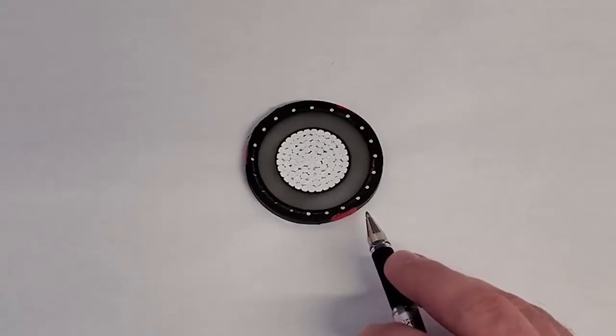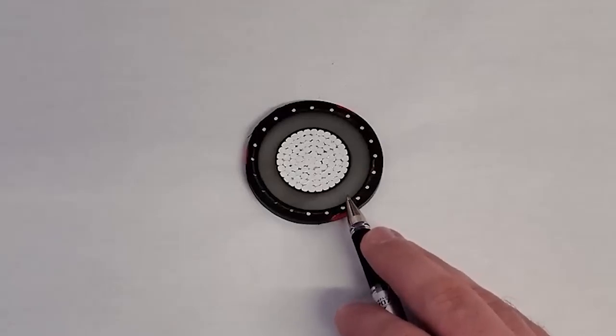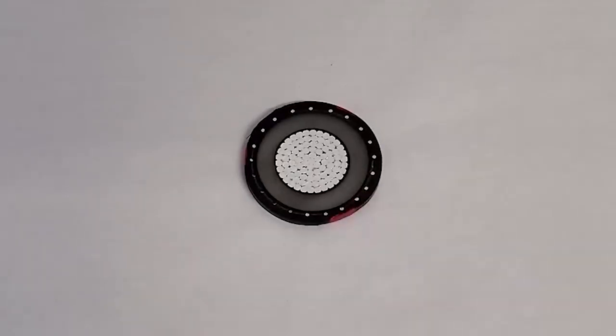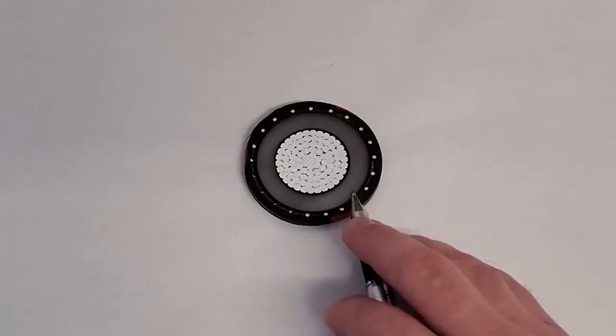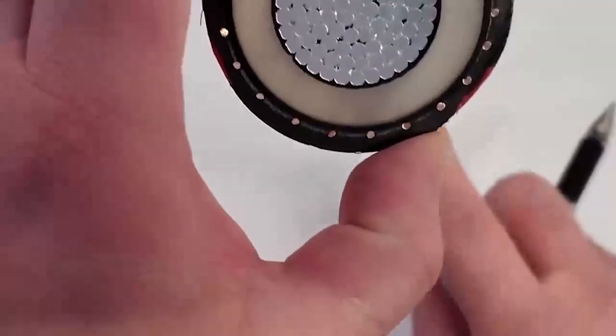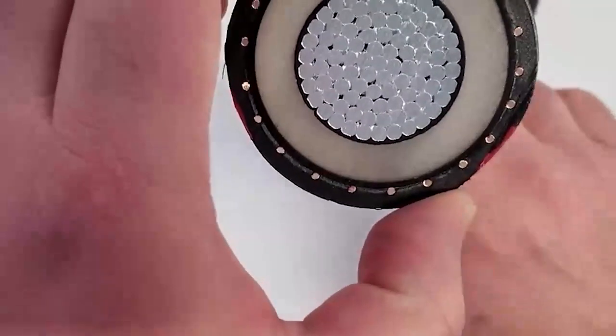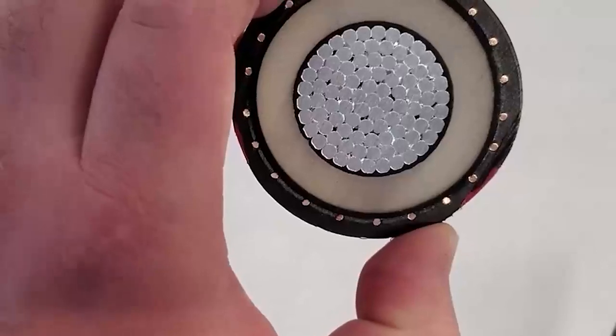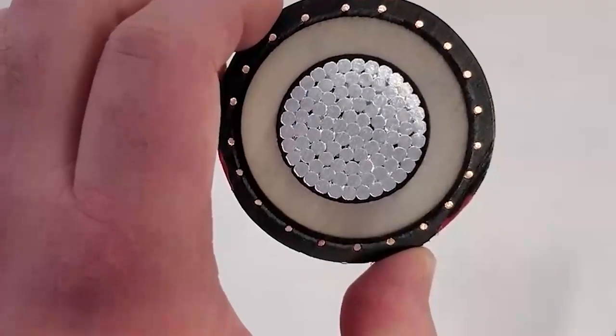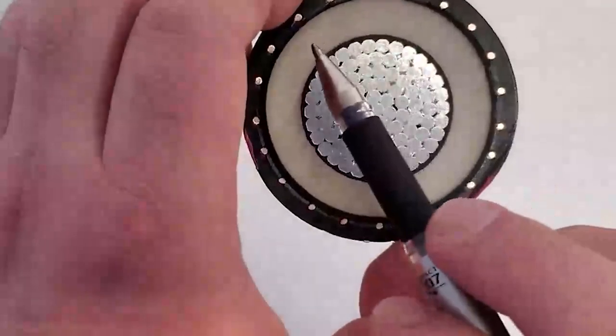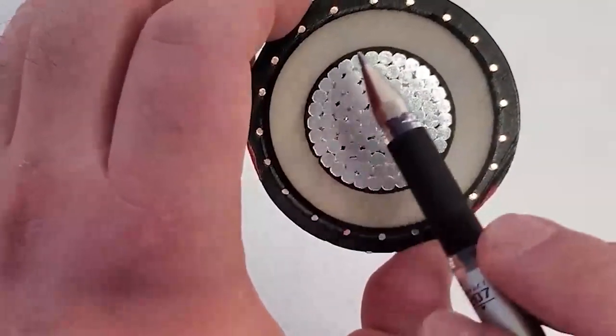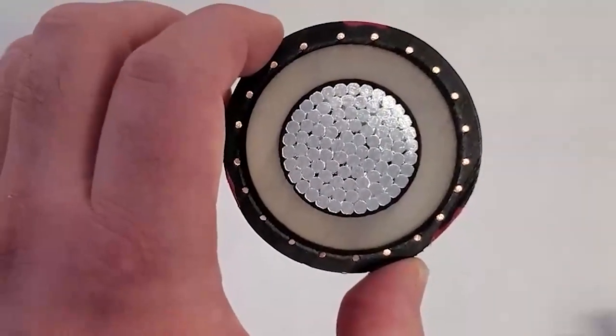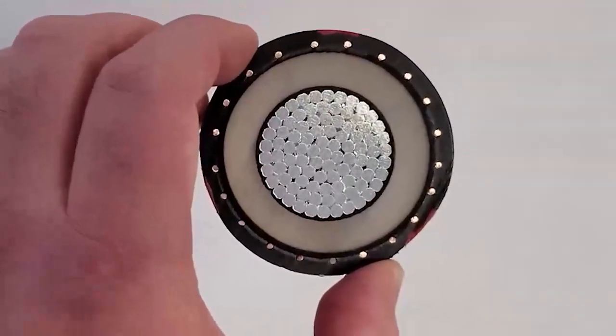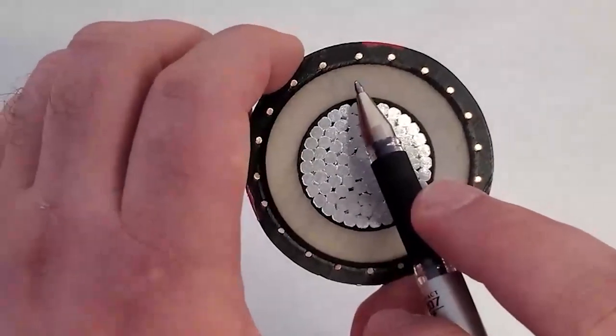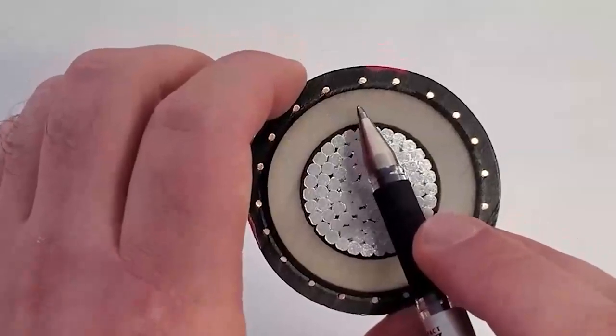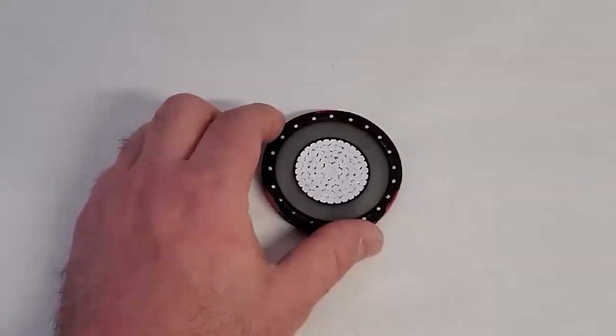If you've got transient voltages and things like that, that you want to make sure don't break your insulation down over time, that's when you'd see things like that. This here is 100% insulation, and it's called XLPE, and it's actually fairly transparent. I don't know if you can see that too well. It depends on the thickness that you cut this. An interesting fact: when you send this in for testing, they put it in a hot oil bath, and this white insulation actually turns clear, and you can see any type of inefficiencies in this cable. If you're doing PD testing, you can identify bad sections of cable, and usually when you do that, you get a microscope and you can actually see a miniature bubble or two in there. So it's really kind of a crazy process.